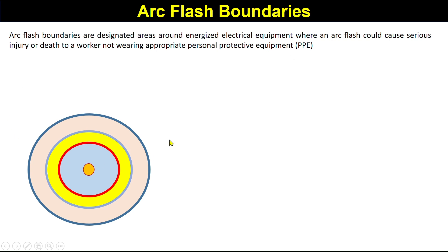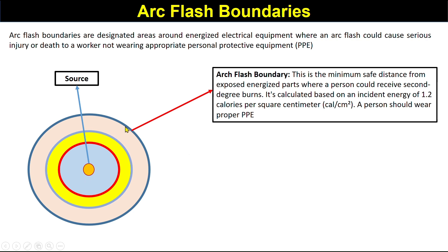The outermost boundary around the source equipment is called the arc flash boundary — this is the minimum safe distance from exposed energized parts where a person could receive second-degree burns. It is calculated based on an incident energy of 1.2 calories per square centimeter. A person must wear proper PPE within this boundary.